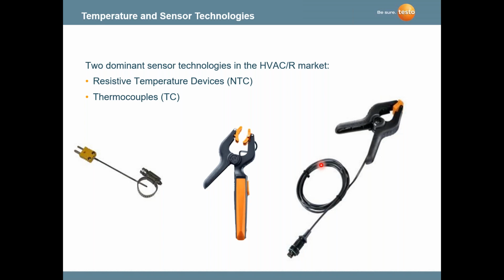NTC probe, as temperature goes up, resistance goes down. It's a little bit easier for us to measure. Type K thermocouple has two dissimilar metals joined together, and we're measuring the voltage change. As voltage changes because of temperature, we get the temperature change, which we can output on an analyzer.